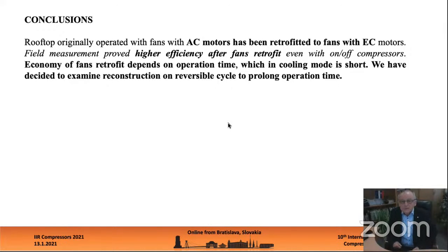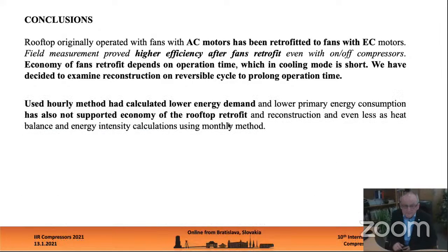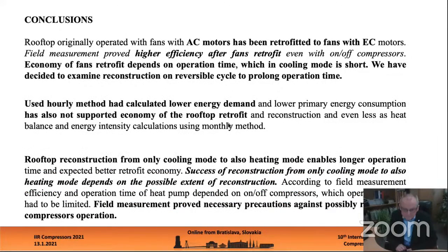We have decided to examine reconstruction to a reversible cycle to prolong operation. The hourly method used had calculated lower energy demand for heating mode, and in this way the hourly method has not supported the economy of the rooftop retrofit and reconstruction.